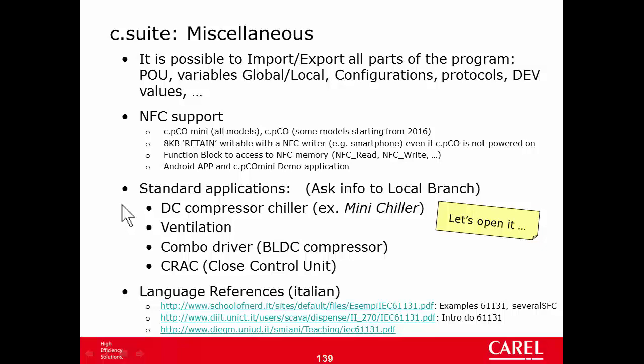The DC Compressor Chiller application manages the electronic expansion valve and the functions necessary to manage the compressors, like the envelope and the oil. It also manages the other devices of the unit, like the evaporator pumps, the condensing fan, the condensing pump, and so on. Later in this video I will open it and show it. The second standard application is Ventilation.